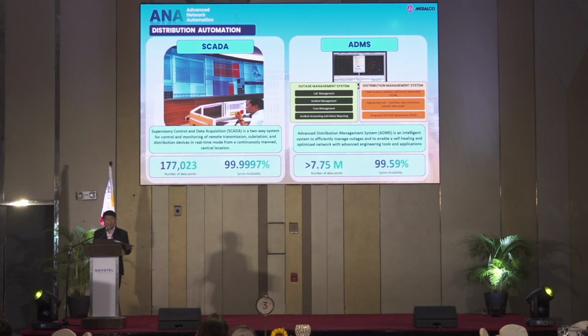In tandem with SCADA, we have this ADMS. If we consider SCADA as the heart, ADMS is the brain. ADMS consists mainly of two systems, the outage management system and distribution management system. So whenever you call the call center of Meralco, your call will be forwarded to our operators manning the ADMS so that they can immediately dispatch our crews. Through ADMS, we can simulate the load flow, the fault magnitude, and we can easily identify the location of the fault anywhere in the distribution lines. We can also accurately predict if the trouble is caused by a simple wire down on the service drop, an outage of a distribution transformer, or even an outage upon the entire distribution line. So that is how the ADMS operates, and its availability is 99.59%.